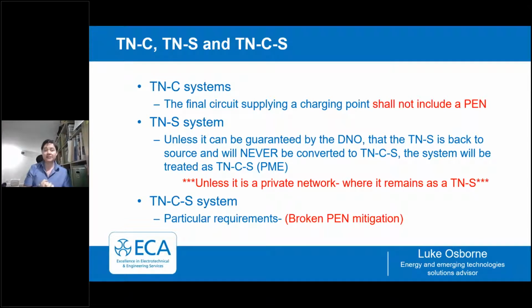A number of buildings have TNS connections to them, but unless it can be guaranteed by the DNO that the TNS will never, that it is TNS back to the source and will never be converted to a TNCS PME system, the system must always be treated as TNCS. This doesn't apply to private networks where they will probably own the substation and it will always remain as a TNS, as the customer has full control of that. So you can install electric vehicles with no additional protection on a TNS system if it's private.